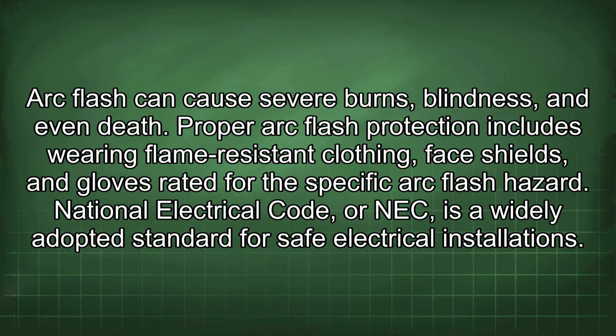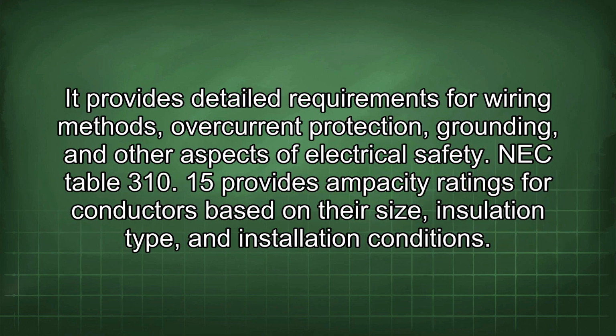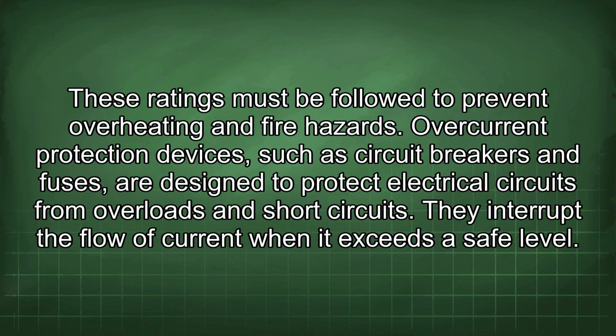National Electrical Code, or NEC, is a widely adopted standard for safe electrical installations. It provides detailed requirements for wiring methods, overcurrent protection, grounding, and other aspects of electrical safety. NEC Table 310.15 provides ampacity ratings for conductors based on their size, insulation type, and installation conditions. These ratings must be followed to prevent overheating and fire hazards.